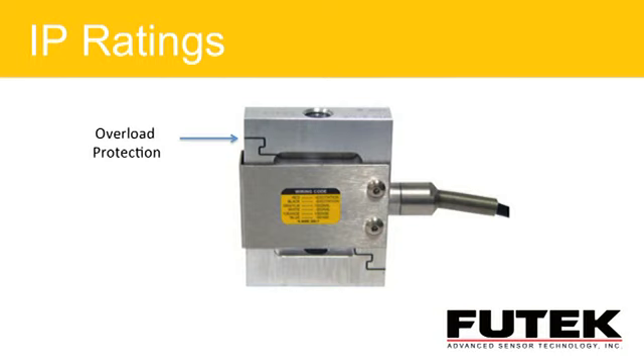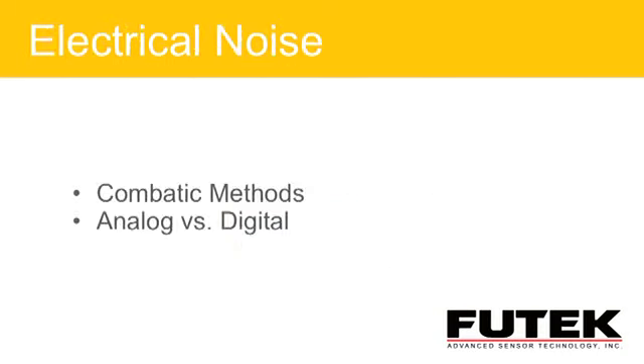So electrical noise, this one I've got to tell you guys, this is a pretty tricky one, especially trying to combat some of the noise issues that may be occurring in your environment. Is there a motor where you have a lot of noise generated? The one thing I can tell you is do not run your sense lines or sensor line cables parallel to any of your power cables. Try keeping them as far away as you can.